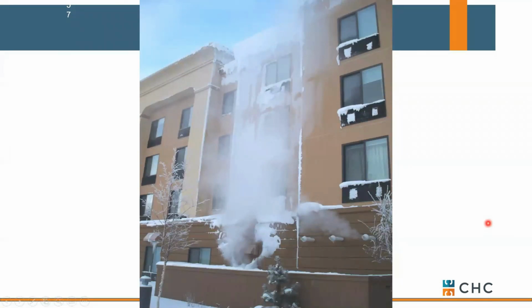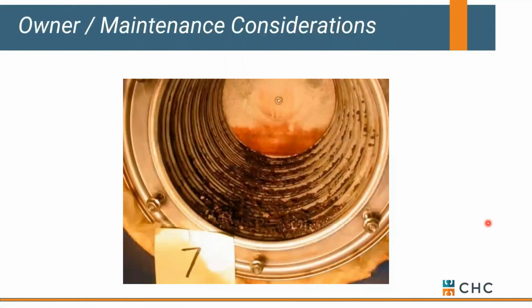Typically in Alaska, all the boilers vent straight off the roof with exit cones with the goal of getting that moisture away from the building. If we're going to go with a condensing boiler, you have to make sure to maintain it. It's a high efficient appliance that also needs annual maintenance to make sure things are clean, make sure combustion is stable, make sure air filters are getting serviced. So what you're seeing here is where the water level or condensate level reached on the back of the burner wall, simply because it won't drain through a clogged or dirty heat exchanger.